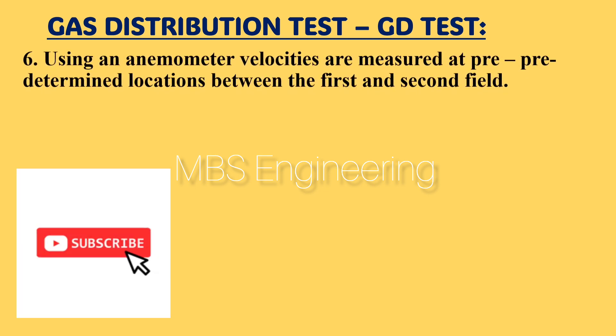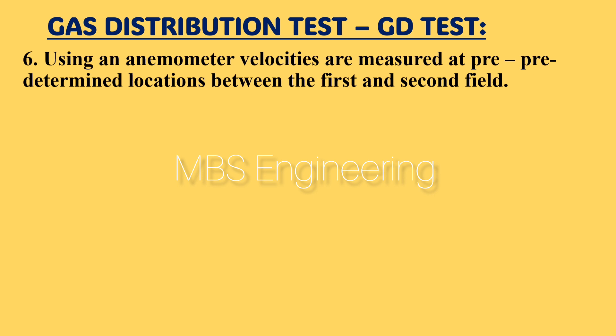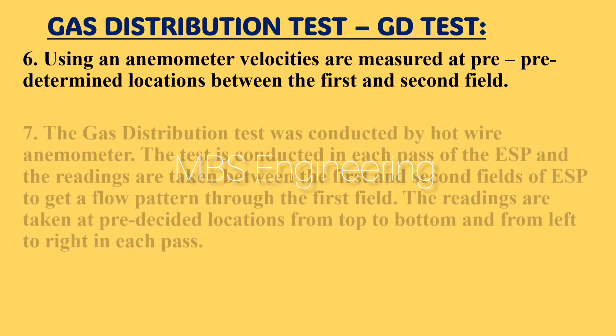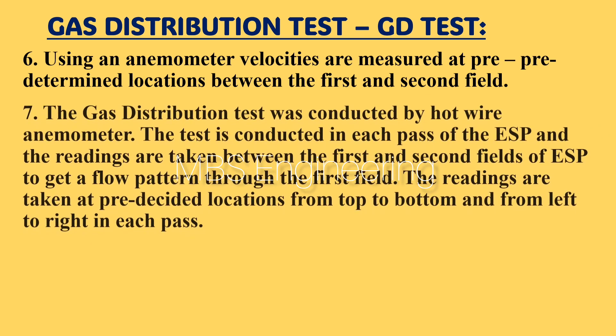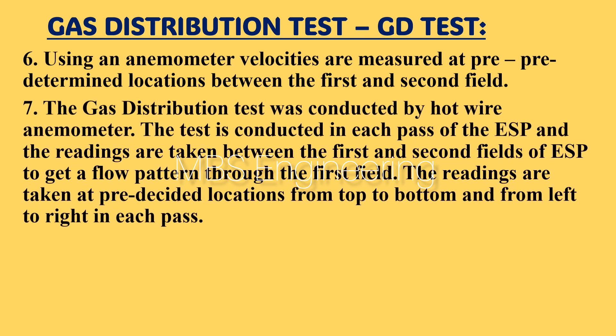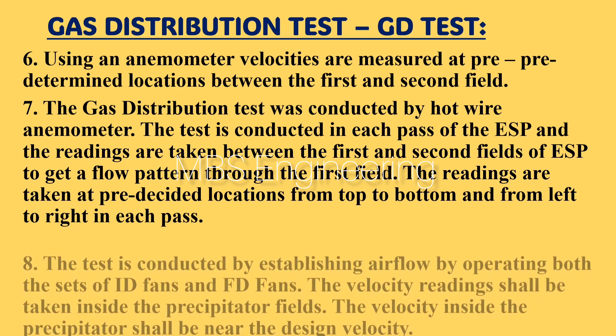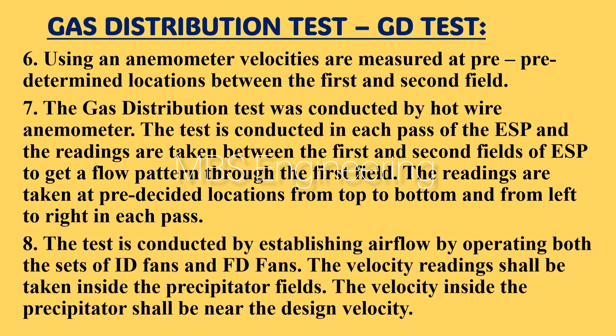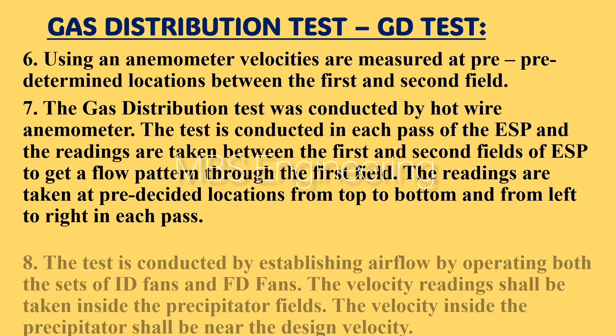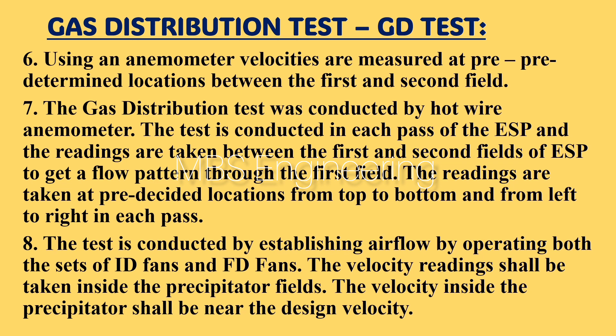Point 6: using an anemometer, velocities are measured at predetermined locations between the first and second field. Point 7: the gas distribution test is conducted by hot wire anemometer in each pass of the ESP; readings are taken between the first and second fields to get a flow pattern through the first field, taken at pre-decided locations from top to bottom and left to right in each pass. Point 8: the test is conducted by operating both sets of ID fans and FD fans; the velocity inside the precipitator shall be near the design velocity.